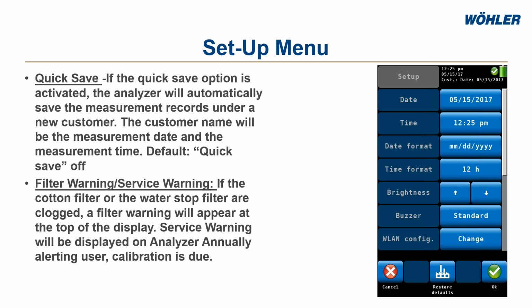Another nice feature I always recommend is turning on the filter warning and service warning. The filter warning, if enabled, will allow the analyzer to tell you if one of your filters is clogged or damaged and needs replacing. The analyzer detects the airflow stoppage or an error and throws up the alert. I also want to note that once you get the filter warning, it won't be erased until the problem is solved and the analyzer is restarted.